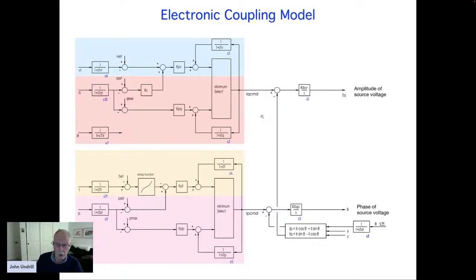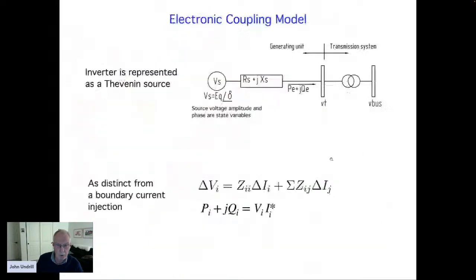The controllers operate on the amplitude and angle of a voltage controlled source. So if we go back here, the generator can be represented as a Thevenin equivalent with a voltage controlled source where we have control of the amplitude of the voltage, we have control of the angle, and there's an impedance of the Thevenin impedance for the system, connecting it to that large transmission network that we were that's operating at a common frequency.